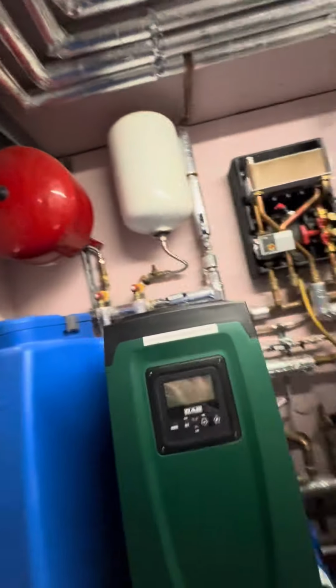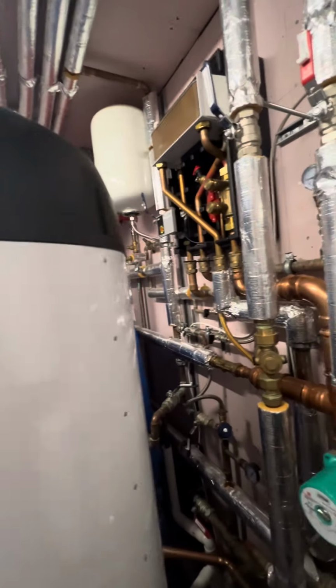And this, I would say, is far too many pumps, and the pipework can be sized so we require fewer pumps. But the reason this is done is because it looks like the installers have been provided with a one-size-fits-all schematic. They've not had a bespoke system design.